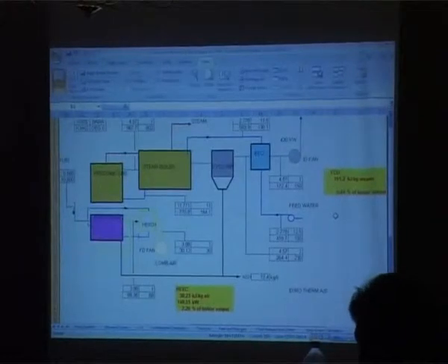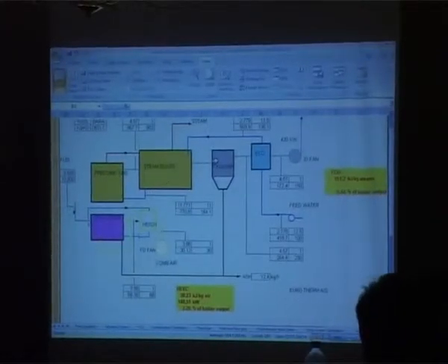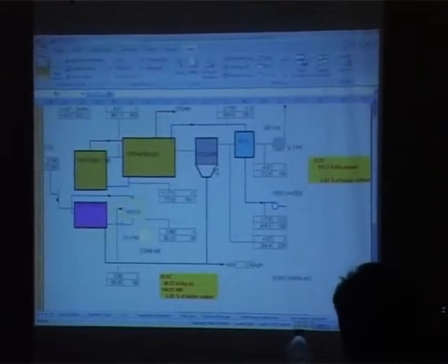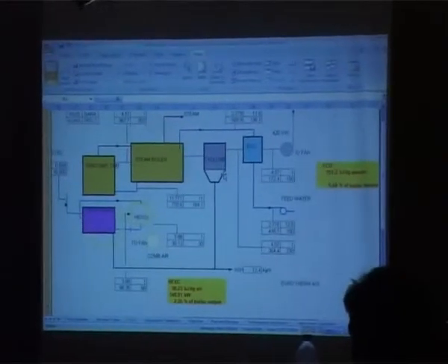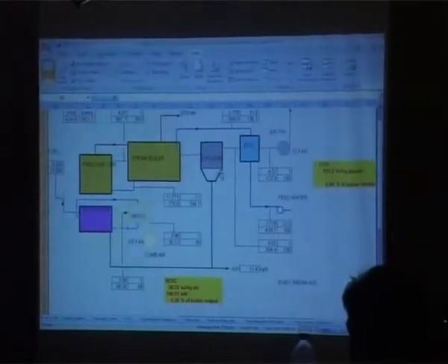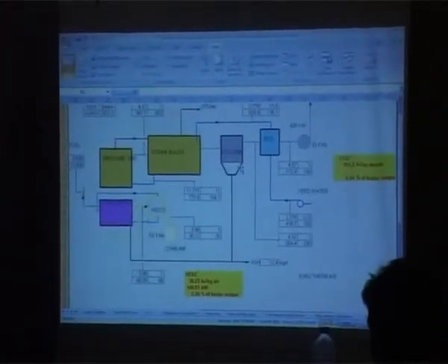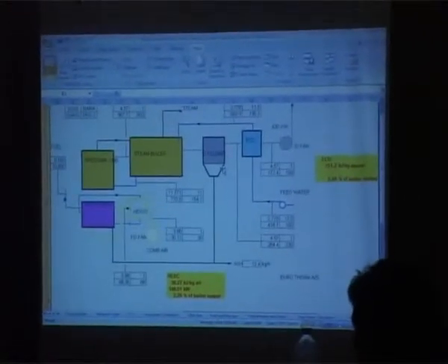It's always a balance. I have been working a little bit on a huge factory making glass in Thailand, and they have a flue gas temperature outside the kiln at I think 560 centigrade. And what they're doing, they take the flue gas and mix ambient air into the flue gas before it goes to the stack. And I said, are you aware of how much energy you're wasting?